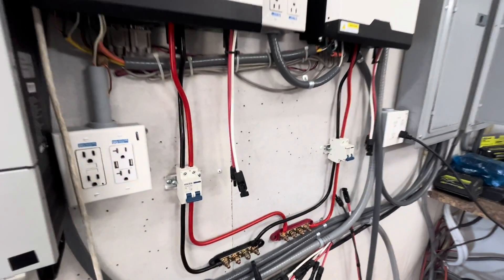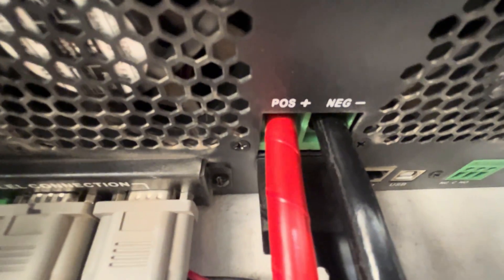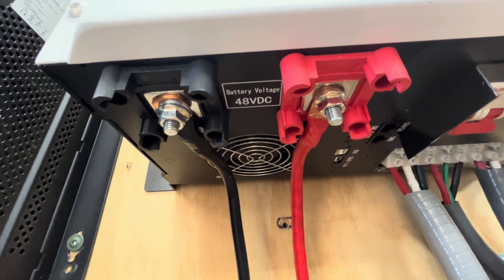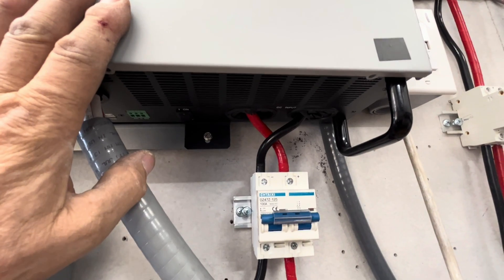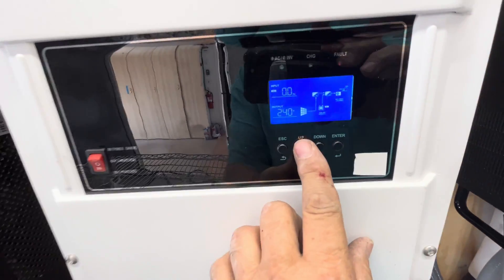We have these new breakers installed here and we just ran all this wiring. This is really interesting — on these MPP Solar units, the negative is on the right and the positive is on the left. So when you go to wire these up, you can't go straight shot down. You have to crisscross the wires. There's a half-inch air gap there on that one, and there are air gaps on that one and that one as well.